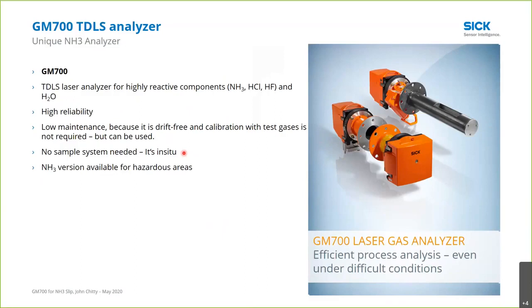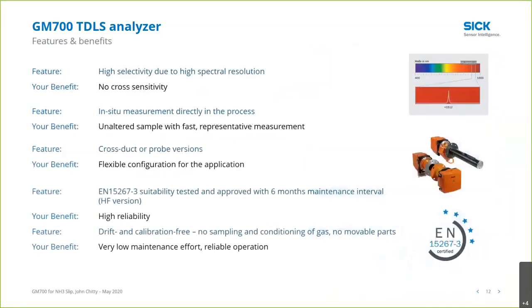There's no sample system, so there are no sample system complications. It's 100% in situ, and the ammonia version is available for hazardous areas with a Class 1 Division 2 rating or ATEX. It features high selectivity due to the high spectral resolution. There's no cross sensitivity. It's in situ measurements directly in the process. So it's an unaltered sample with a fast response. We offer both a cross-duct version and a probe version, so it's very flexible.